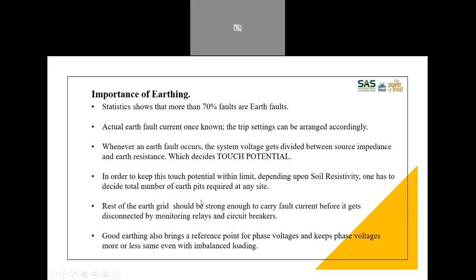Then one should know that getting earth pit resistance of less than 1 ohm is a myth. I mean, you just cannot get less than 1 ohm at every place. So that tells you, depending upon soil resistivity, how many earth pits you should have.